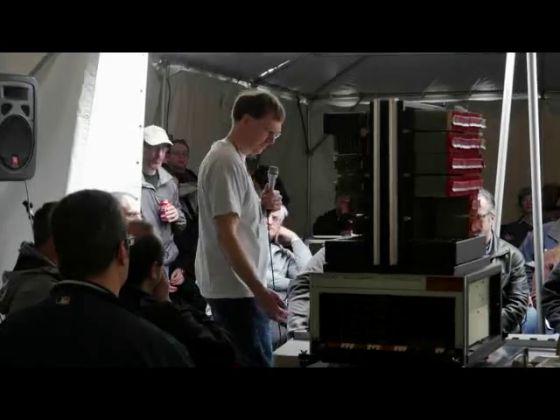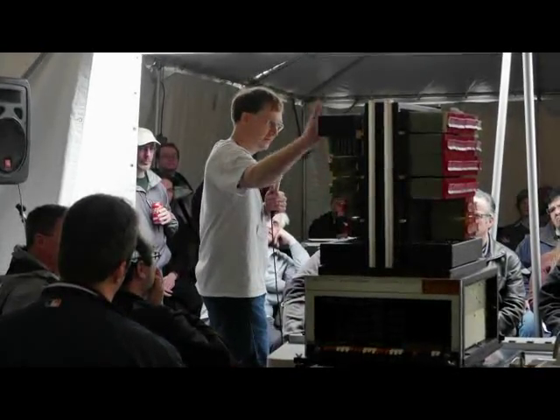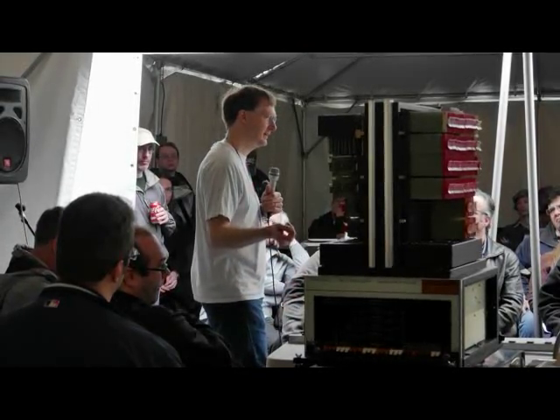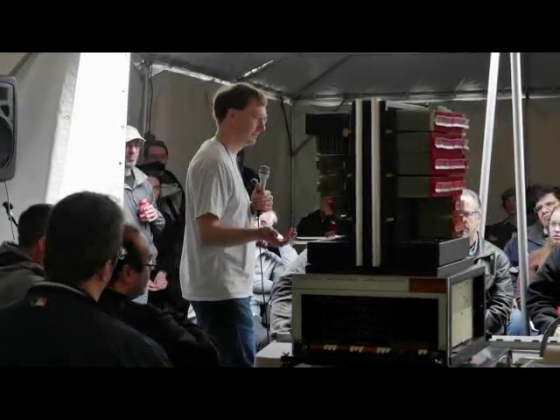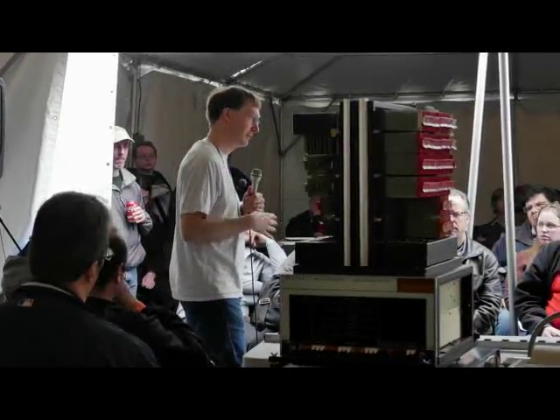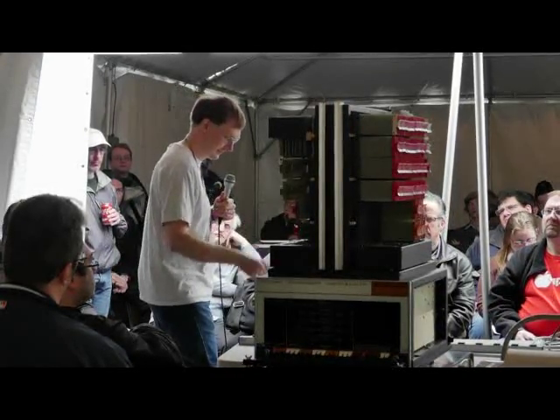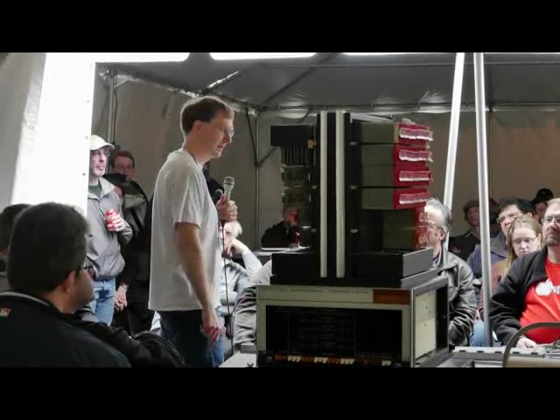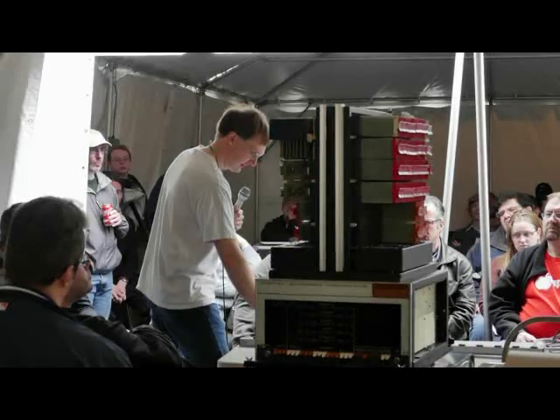There's several types of capacitors. The aluminum electrolytics are the big ones, and there's a couple other spots. There's hermetic tantalums, which are quite reliable. There's a mil-spec type. This one doesn't have any. Another really trouble-prone capacitor is the dip tantalums, but luckily it only has the other type, and it has a couple electrolytics, the little smaller ones in the back lane. One of them was bad that I had to replace.